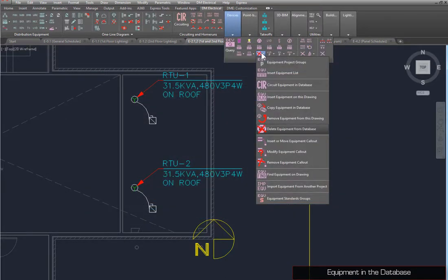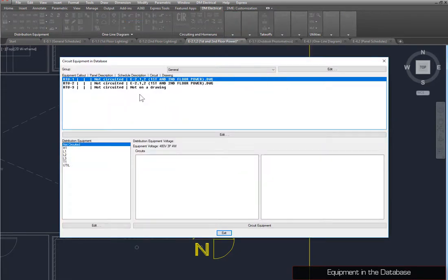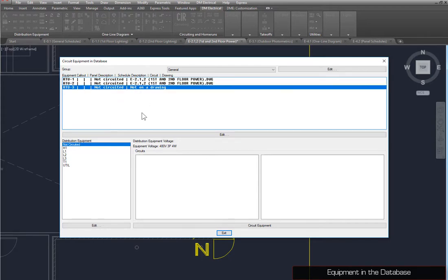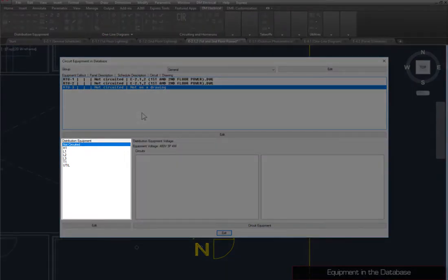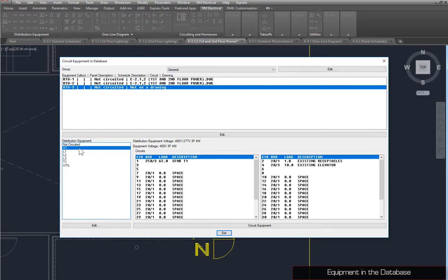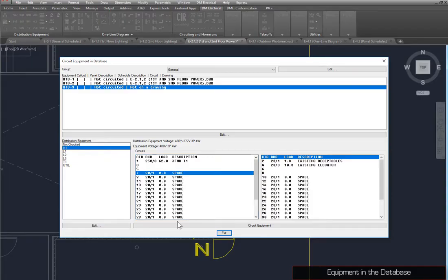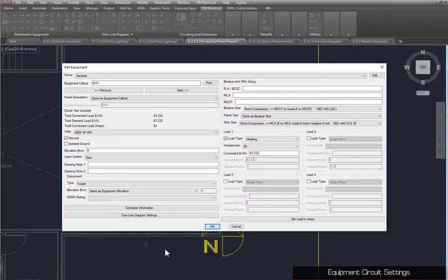To circuit equipment connections, you can use the Circuit Equipment in Database command. To circuit RTU3, select it from the top list. Select Panel H1 from the Distribution Equipment list, select Circuit 7, and press the Circuit Equipment button. You can make changes to this circuit for equipment connections, such as breaker and wire sizing, using the Query Device command. We've created and inserted a new equipment called AHU, which has voltage and load 1 set as shown, to demonstrate.